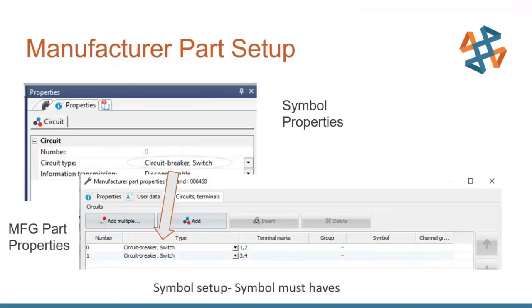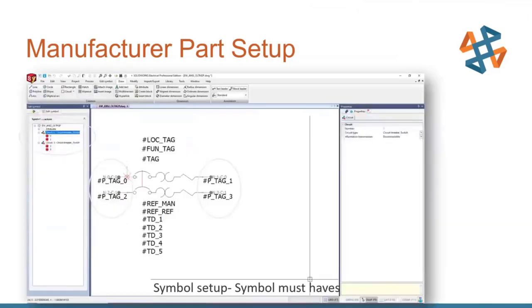When it comes to using intelligence for manufacturer parts, we also want to set up our symbol property information and any manufacturer parts properties that go along with the circuits for that symbol. So in other words, our manufacturer part has information. It knows what connection points it's looking for and we want our symbol to match so that the software can confirm for us that we're actually using a manufacturer part properly in a schematic. So here's a symbol and what we have circled here is essentially our circuit information. So whether a device is one circuit, four connections per circuit, or maybe it's two circuits, two connections per circuit, we want to set that up. It needs to match our manufacturer part to get the most out of that information and that will help us in 3D as well.